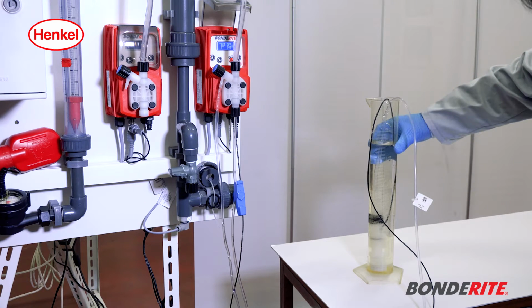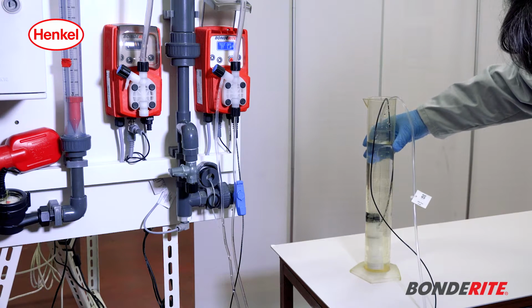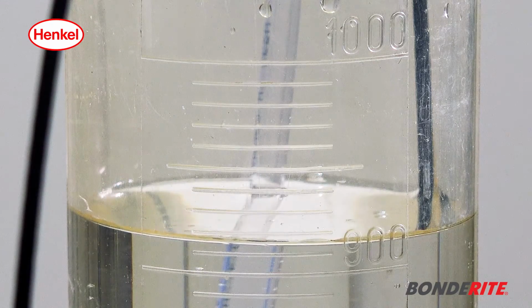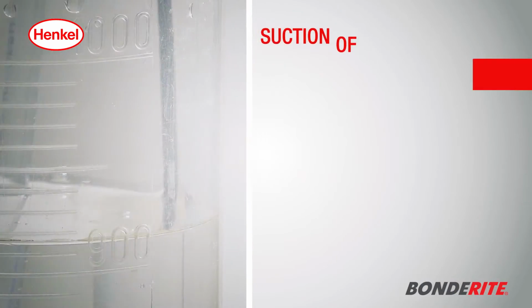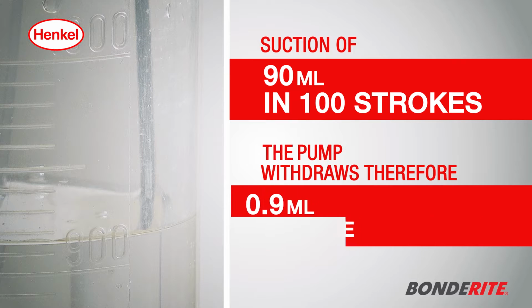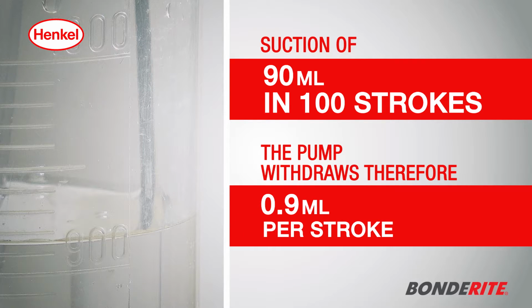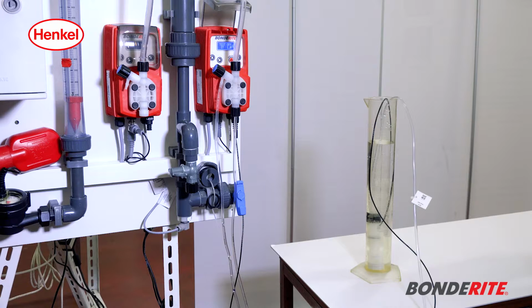We now verify the amount of milliliters that the pump withdrew: 90. That means that, per each stroke, our pump withdrew 0.9 milliliters. That is now what we set on the pump.